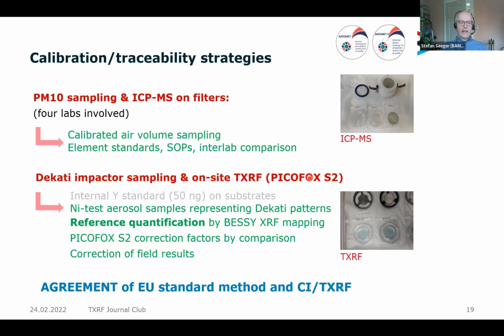On the other hand, if you use TXRF in combination with impactor sampling, the situation is quite different. Quite usually, internal standards such as yttrium are applied on substrates, and we did it in a different way. As I said, normally these internal standards are applied directly in the middle of a substrate carrier in the form of microdrops. But we have a different situation here.